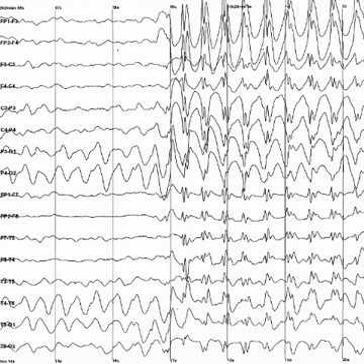Linked ears, which is a physical or mathematical average of electrodes attached to both earlobes or mastoids. Average reference montage: the outputs of all of the amplifiers are summed and averaged, and this averaged signal is used as the common reference for each channel. Laplacian montage: each channel represents the difference between an electrode and a weighted average of the surrounding electrodes.